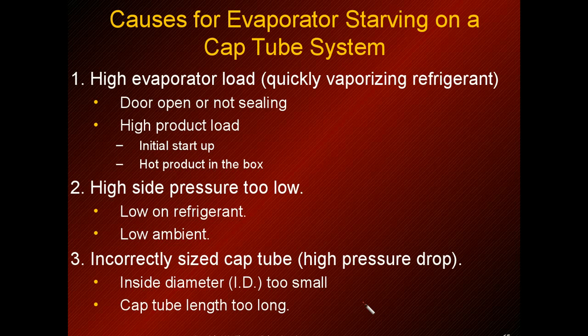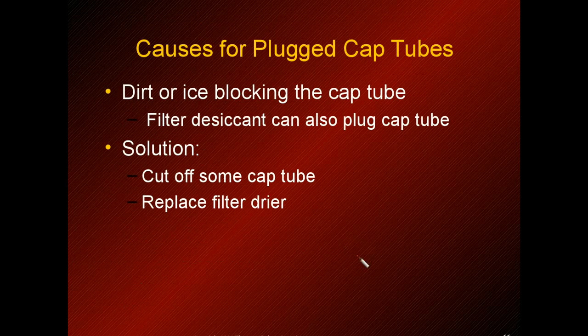For a starving cap tube system, check if the door has been left open too long or if there's a bad door seal. Ask when they put the product in the box — did it come from a cooler or from room temperature? It can take 24 hours to cool room-temperature product down. Low refrigerant charge will also cause a starving condition, as will an incorrectly sized cap tube — though you'd only find the latter if someone recently replaced it and made a mistake.